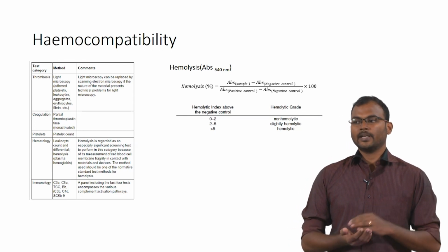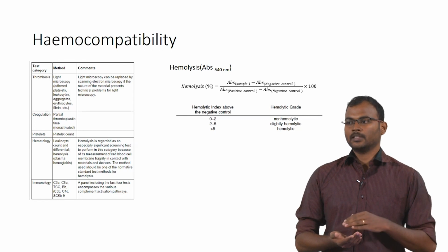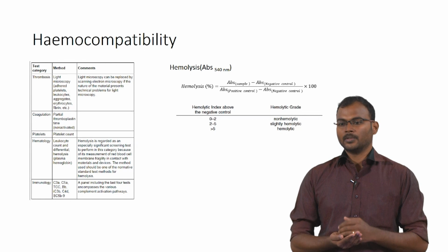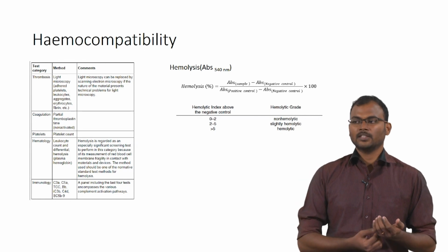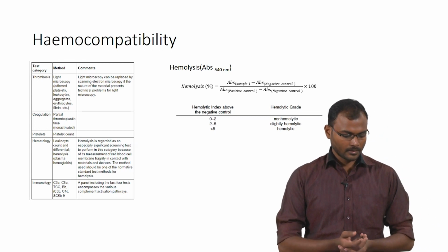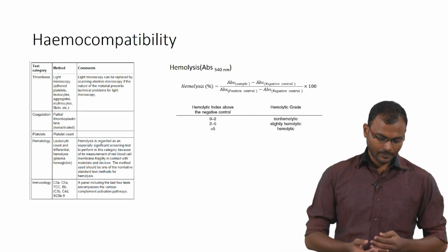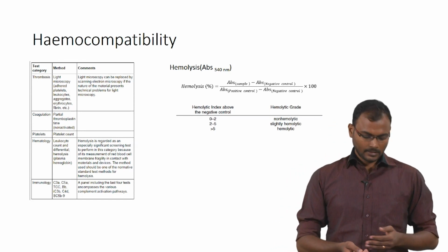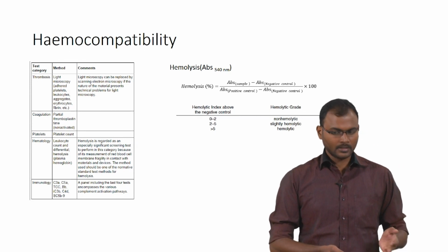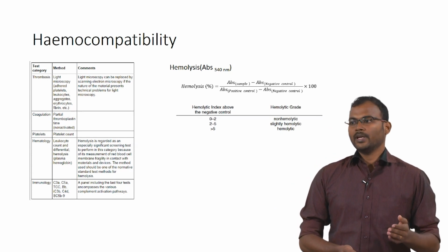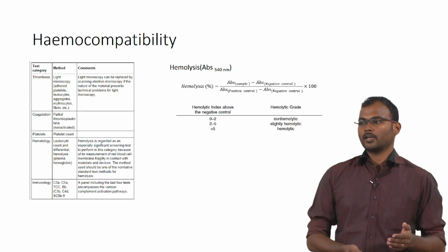If your material is avoiding thrombus formation, there would be a delay in thrombus formation, whereas in the reference material it would be formed immediately. Based on that you find out the partial thromboplastin time, and you can look into markers of the coagulation cascade like C3a, C5a. There is a series of pathways involved in the coagulation cascade.